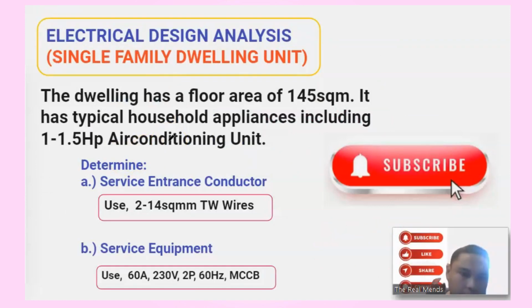Okay, to sum up, para madali yung ma-visualize yung ating output. So for this single family dwelling unit na meron siyang floor area na 145 square meter, typical household appliances including 1.5 HP aircon unit. Okay, so we have here service entrance conductors and then service equipment. So to visualize further, let's construct actually a panel board diagram. Paano yung installation actual? Paano yung manufacturing ng panel board?